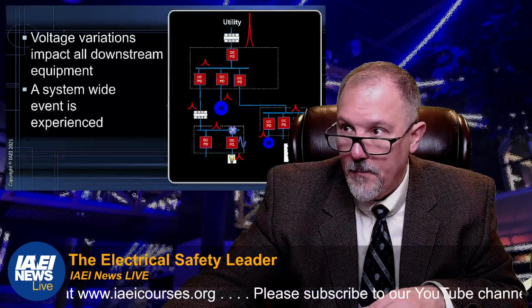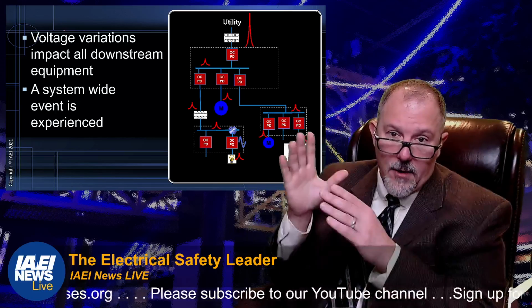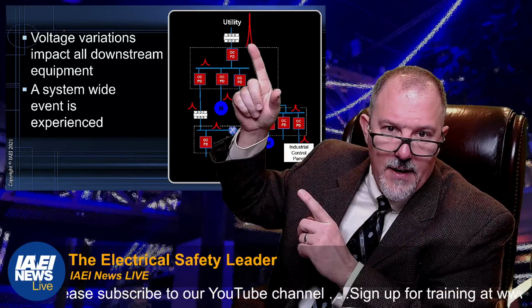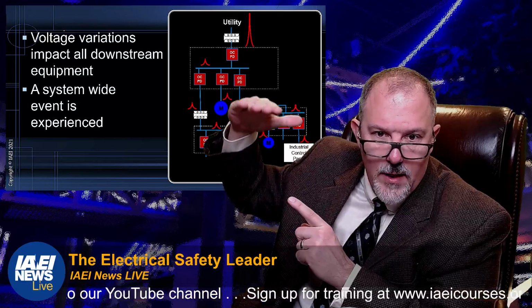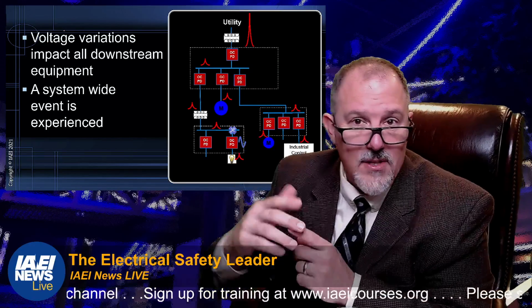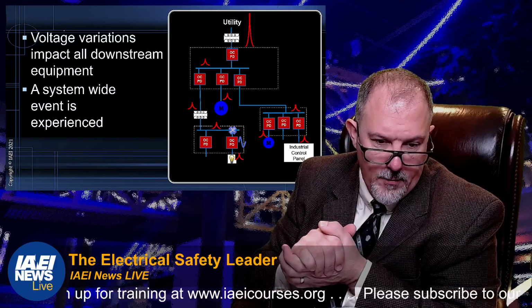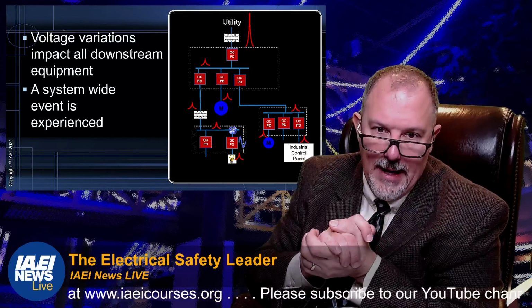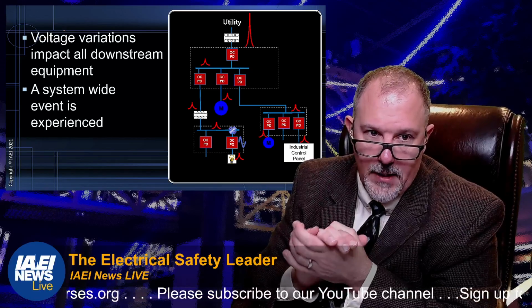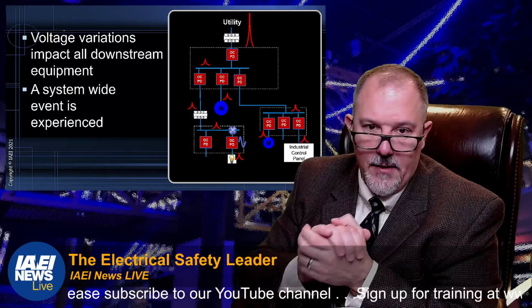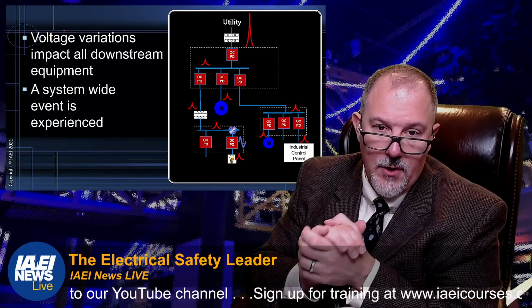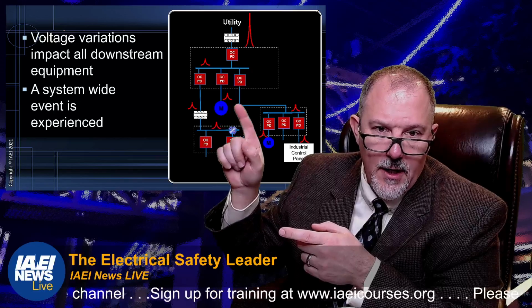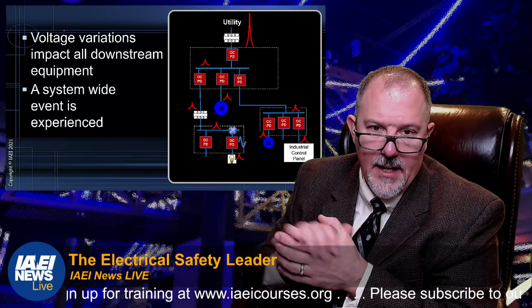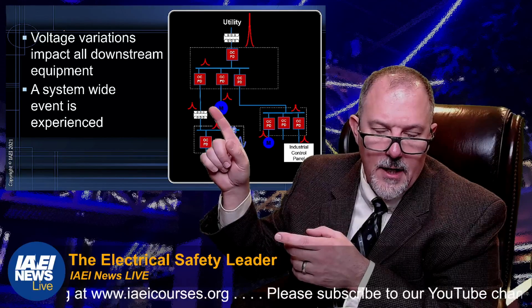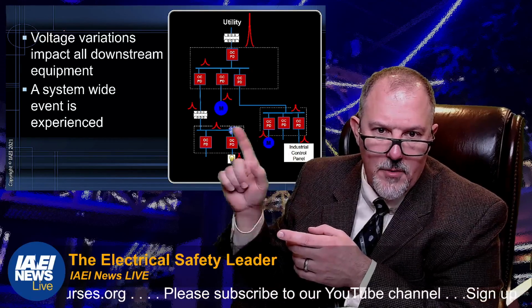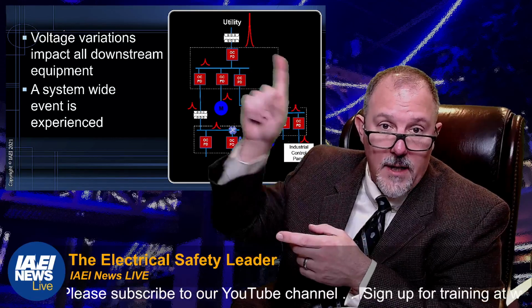All right. We talked about a swell. Now, this was that earlier discussion I had. Remember, when I have a transient voltage event from the utility, it propagates its way down through the entire power distribution system. And obviously, it will be less in magnitude, dampened, so to speak, the further down in the system that we get. Now, keep in mind, too, a transient event can occur at this motor and propagate itself. A transient voltage event can occur because of switching anywhere in this power distribution system. It doesn't always come from the utility.